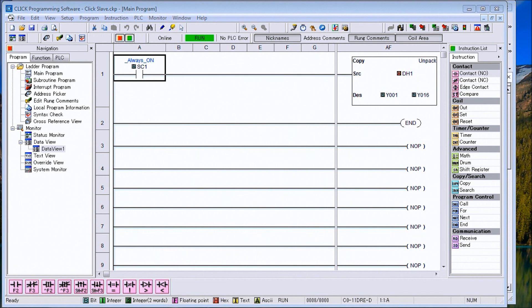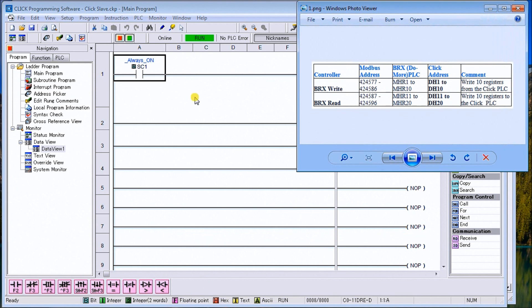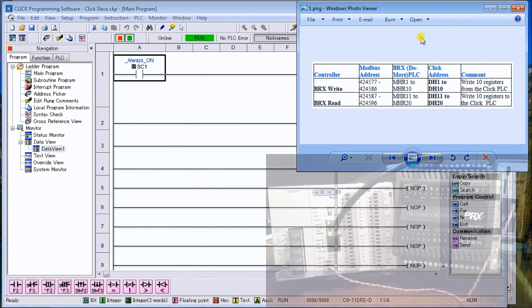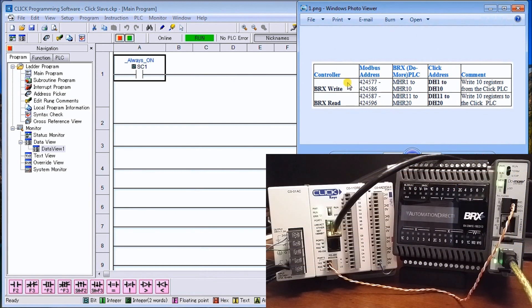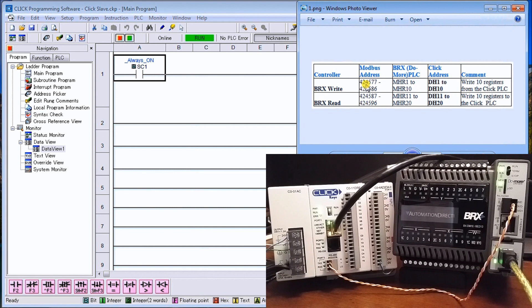Today we're going to be talking about the Modbus RTU remote terminal unit, the BRX PLC master to Click PLC slave communications. Looking at our screen, there's a table showing exactly what we're going to do. From the BRX PLC we're going to write 10 channels using Modbus RTU to the Click PLC, writing to MHR1 to MHR10, with the Click address being DH1 to DH10 and the Modbus address 424577 to 424586.